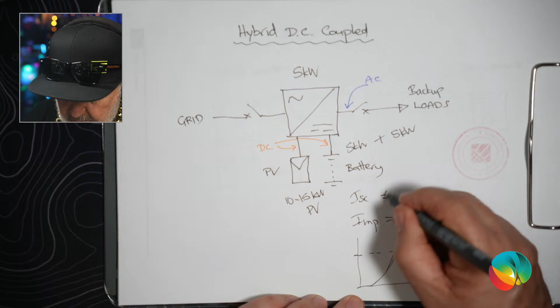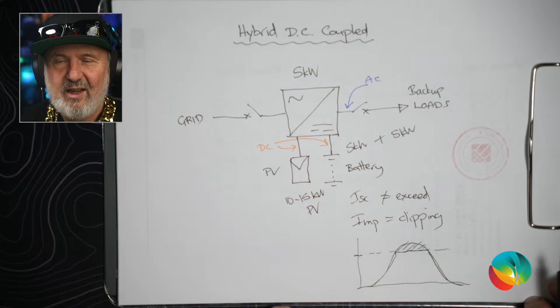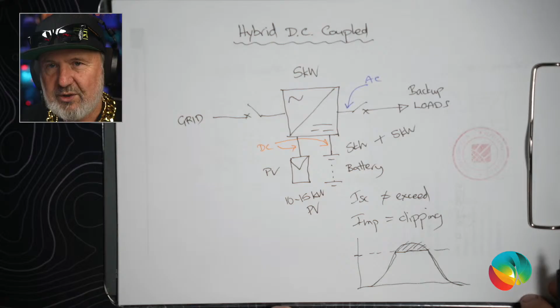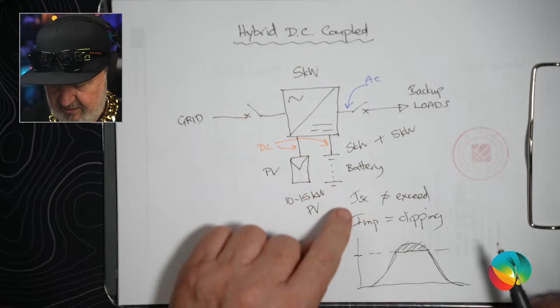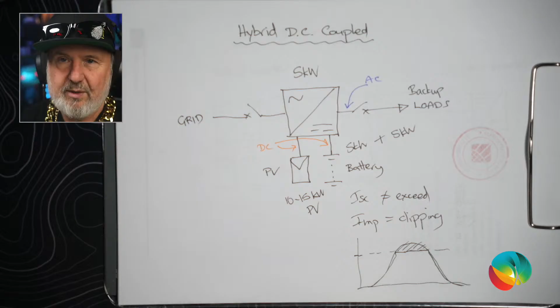But the other number is ISC, so that's short circuit current, and you must not exceed it. Okay, so you must not exceed. And the reason for that is it's actually the current rating of the components. It could be the plug, socket, input circuitry, etc. So if the inverter were to have a short circuit internally or externally and there's short circuit current flowing, you must limit it. Now, how do you limit the ISC? By selection of modules. So the modules will have an ISC value, and you have to ensure that the ISC of the panels is less than the ISC of the inverter's solar inputs.